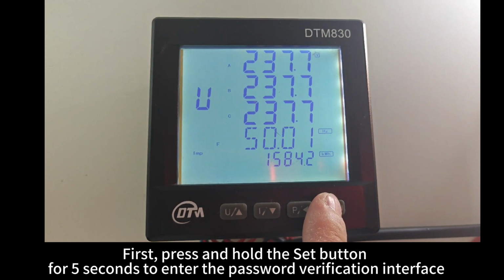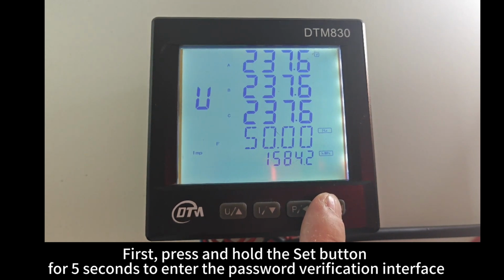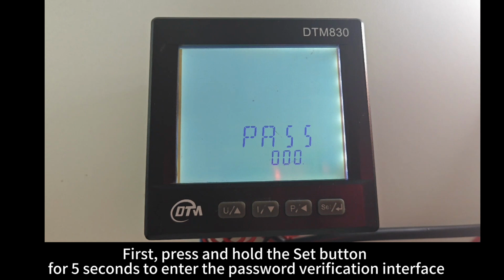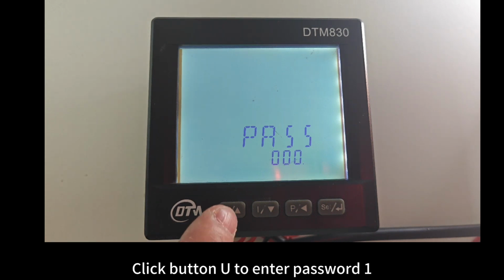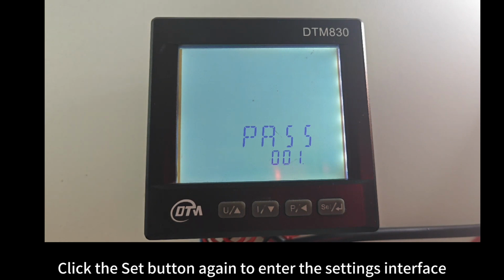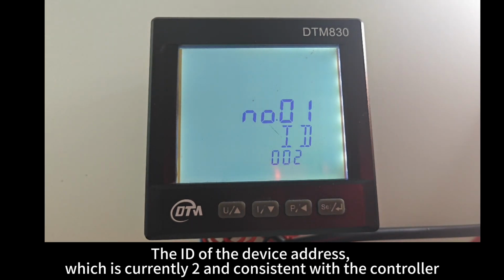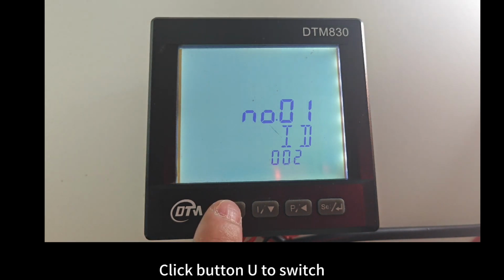First, press and hold the Set button for 5 seconds to enter the password verification interface. Click button U to enter password 1. Click the Set button again to enter the settings interface. The ID is the device address, which is currently 2 and consistent with the controller. Click button U to switch.